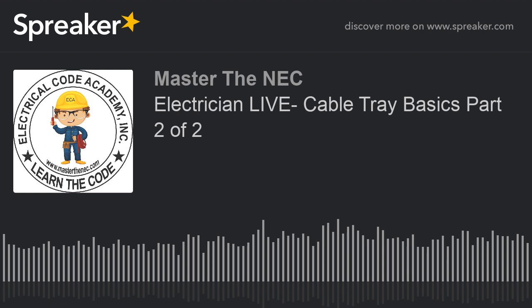No questions here. Okay, now you're going to bring back that question, well, what about those configurations that you talked about earlier, Paul, the triplex, quadplex, what about those? Okay, all right, well, then that's when we get to D. And D says this: where single conductors are installed in a triangular or square configuration in an uncovered cable tray with a maintained free airspace of not less than 2.15 times one conductor diameter. Okay, so it's the largest conductor contained within that configuration. So 2.15 times the OD of that largest conductor contained within that configuration.